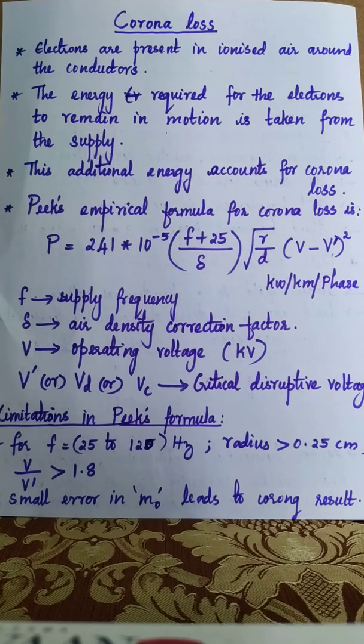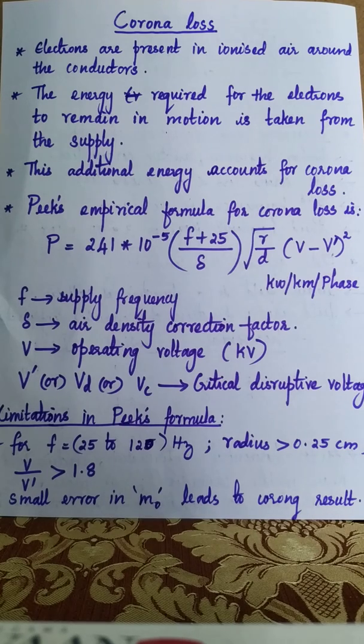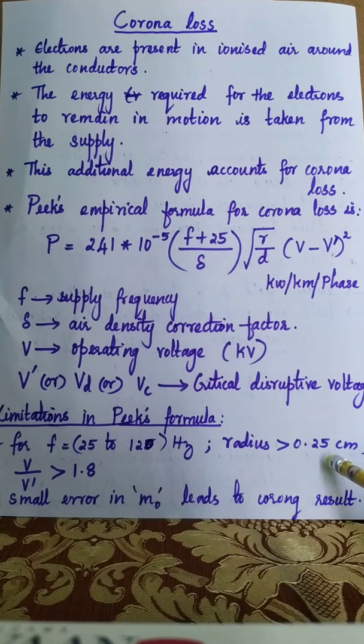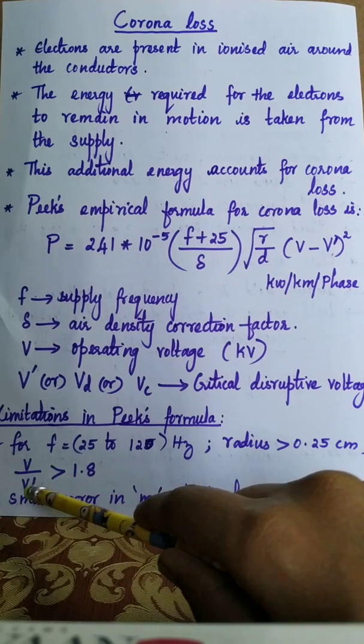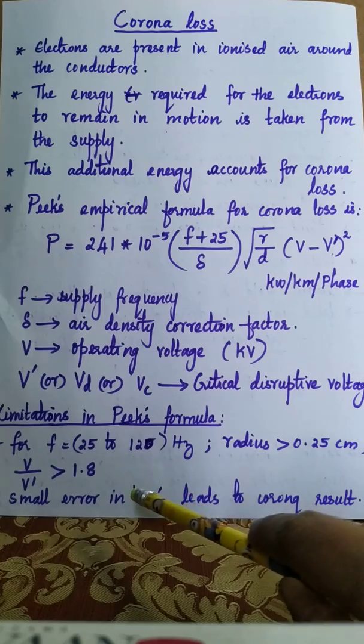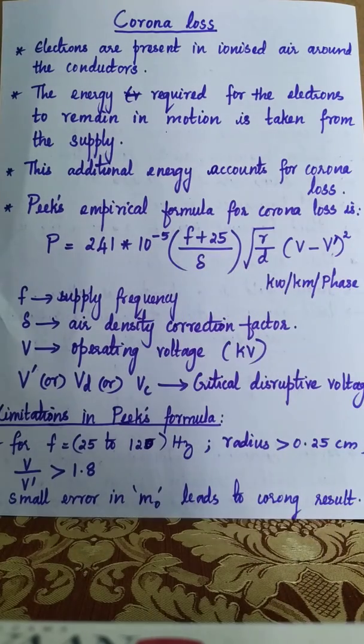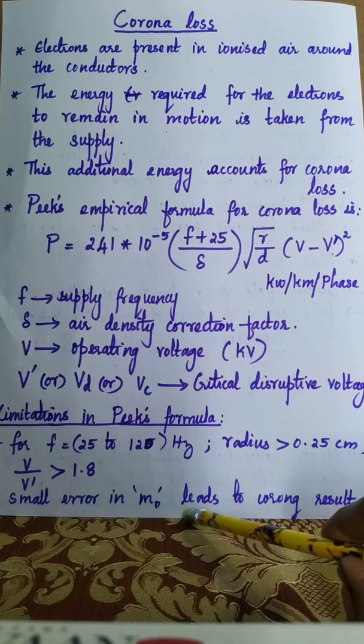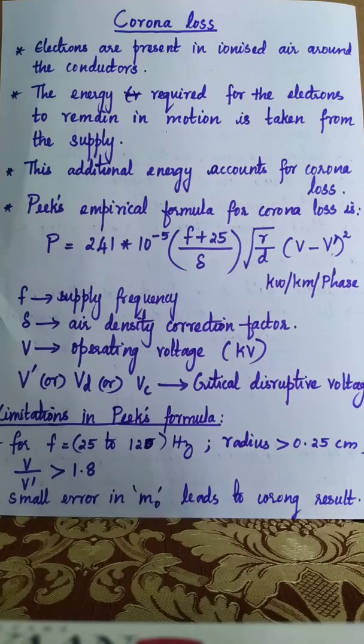The additional energy taken from the supply by electrons to maintain motion and strike air molecules is corona loss. Regarding limitations of Peek's formula: it gives accurate results only for frequencies in the range 25–120 Hz, provided the conductor radius is greater than 0.25 cm and the ratio of operating voltage to critical disruptive voltage is greater than 1.8. Also, a small error in choosing the surface irregularity factor M₀ will make results inaccurate.